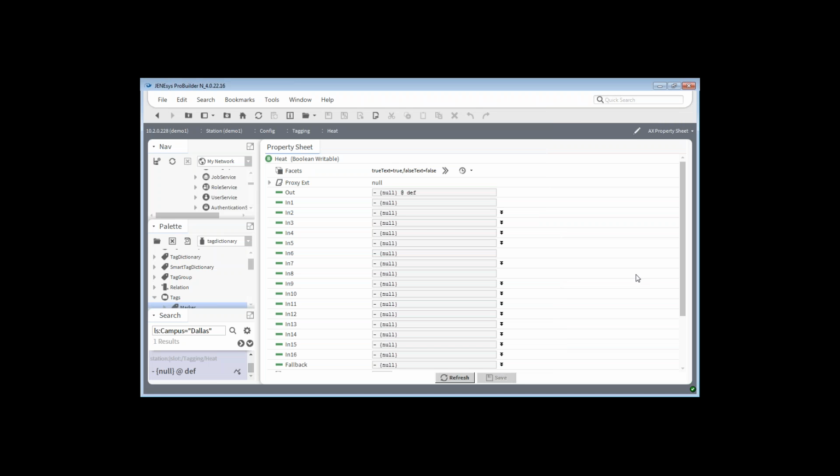It says something like, hey, I'm really interested in finding the current frost set point, or I'm interested in finding the current hot water temperature, outside air temperature. And it looks for those same tags in the new station that it had in the old one, and provided they exist, it'll even wire itself. So I don't even have to go through the trouble of jumping around the station and adding those tags. Now it has a dialogue to make sure that I'm wiring where I want to wire.